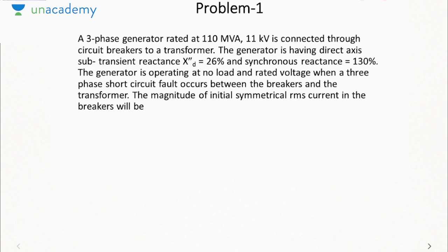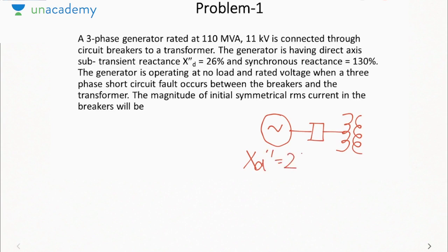It is saying a three-phase generator rated at 110 MVA 11 kV is connected through a circuit breaker to a transformer. Now, first thing, whenever you are given a fault analysis problem and you are being given the configuration of the network, if you are not given the figure, try to draw the figure alongside. So a generator is connected through a circuit breaker to a transformer. The generator has subtransient reactance 26% and synchronous reactance 130%. The generator is operating at no load and rated voltage.